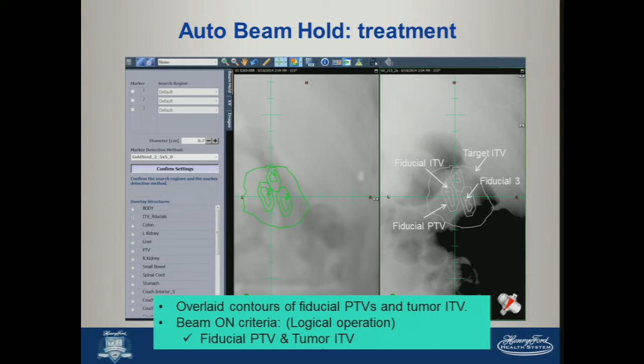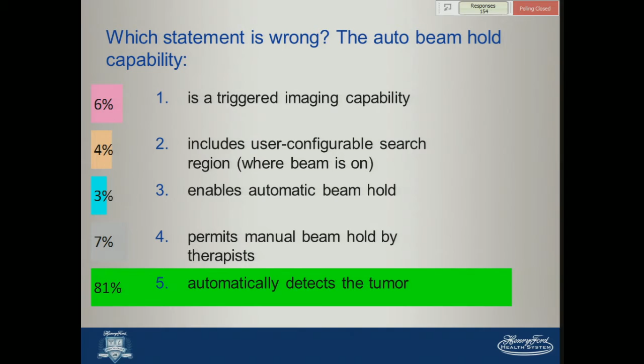So, final Sam's question on auto beam hold. Which statement is wrong? The auto beam hold capability is a triggered imaging capability, includes user configurable search region where the beam's turned on, enables automatic beam hold, permits manual beam hold by therapists, and automatically detects the tumor. Correct. Auto beam hold's designed to detect implanted fiducials, not the tumor. It's not that sophisticated or ambitious. And you can find some details about that in this Varian auto beam hold quick tip document.